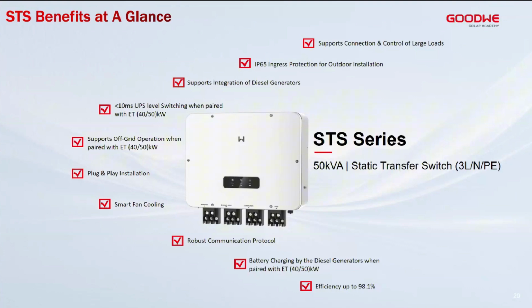The STS also supports off-grid functionality. So if you install the ET 40 or 50 kilowatt inverter with an STS, that system can work off-grid. The grid port can lie idle until you've brought in the grid line. So it's very flexible, it's plug and play. The communication cable from the inverter to the STS comes with the product itself. The ports are already ready, with OT or lug terminal connections. Not much is really needed to install this product. It does come with LEDs at the front to give you the status of the product in terms of communication to the inverter, faults, or in case there's an alarm within the product itself, to inform you of replacement or troubleshooting.